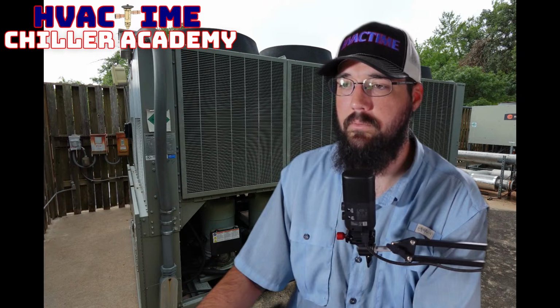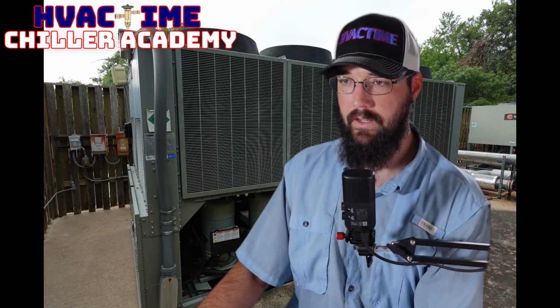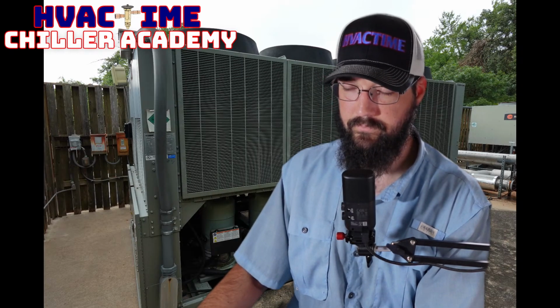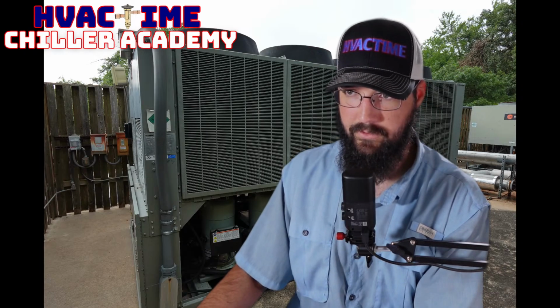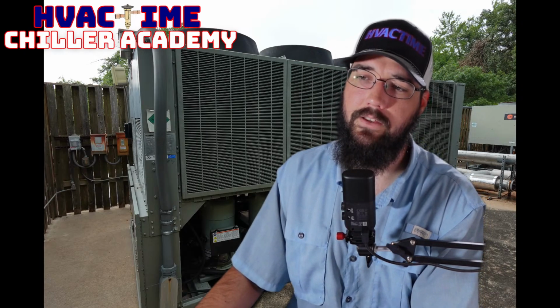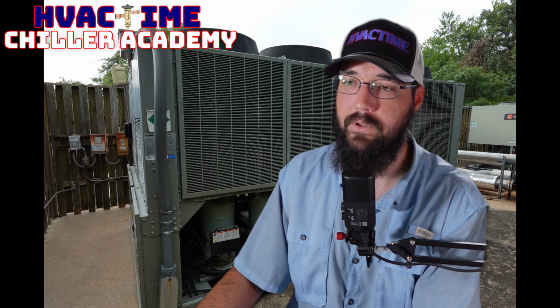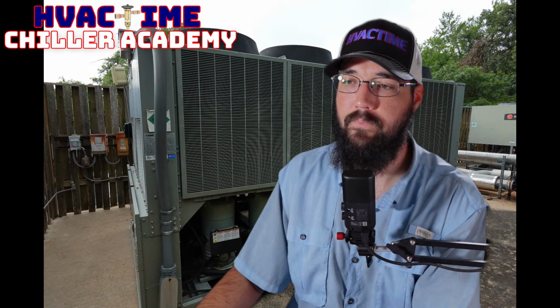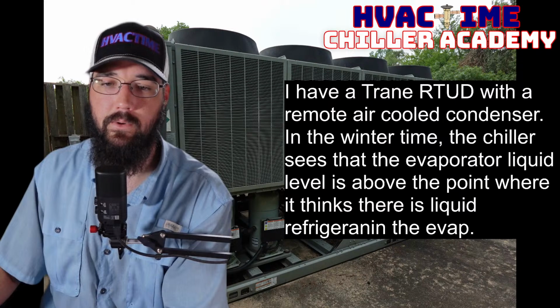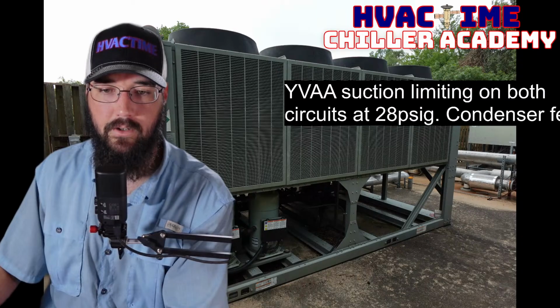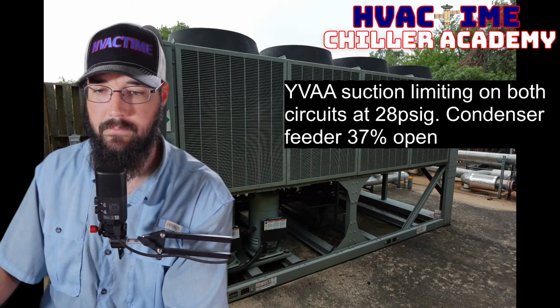YVAA suction limiting on both circuits at 28 psig. Condenser feeder 37% open. Which I recently learned, or realized, maybe a better way to say that, YVAA is controlling the condenser based off of subcooling, which is different from the YCIV. It's interesting how much they changed between the YCIV and the YVAA. You wouldn't think so, but they're actually quite different in terms of machine. Let's talk about this.